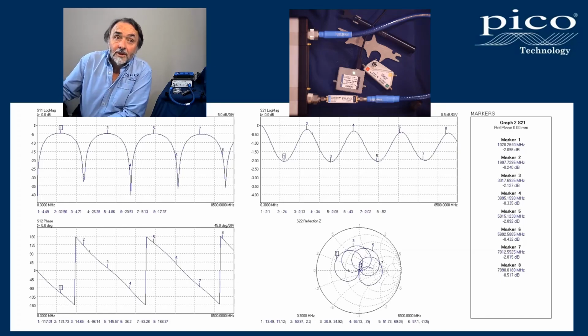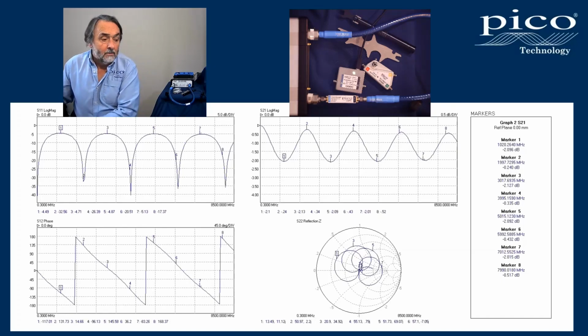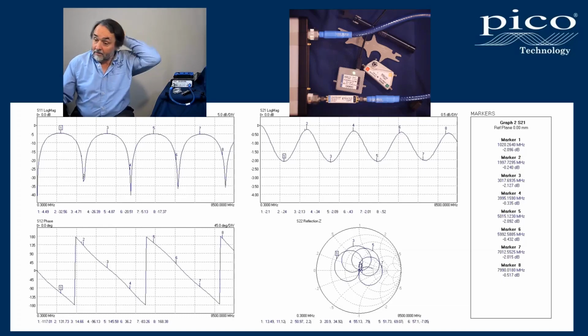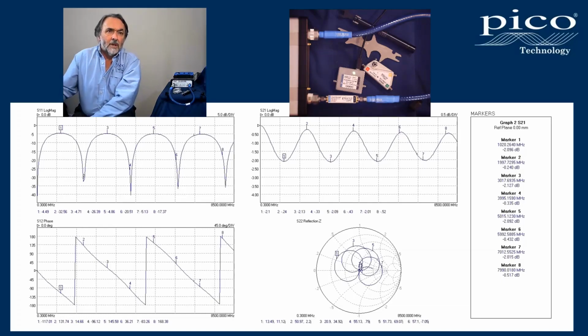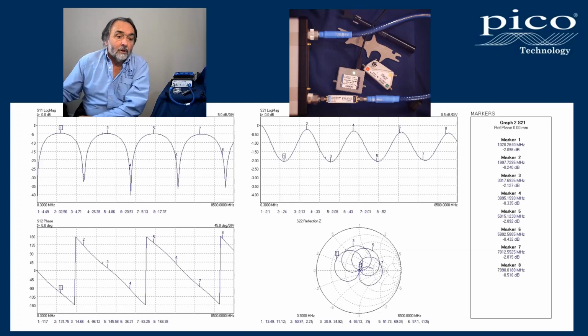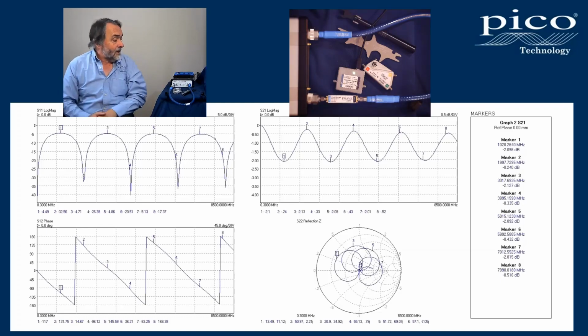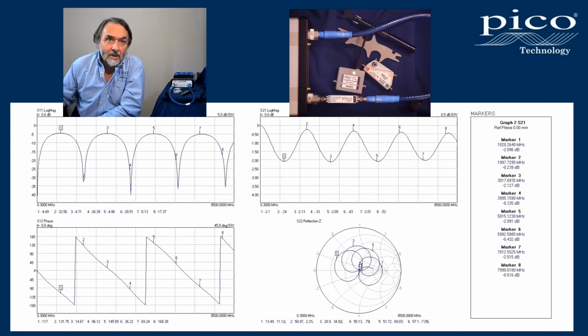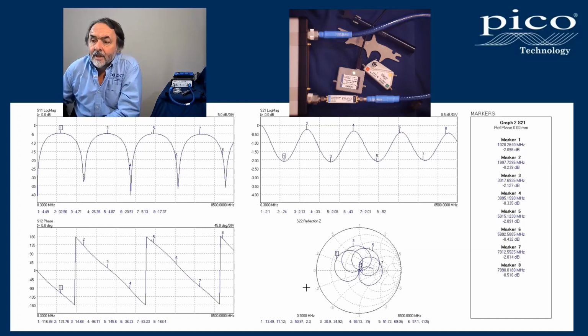We know what this check standard should measure, because the check standard comes with traceable measurement data from its own calibration, and so this measurement should match within the specification of the VNA. This measurement should match its own data. So let's load that data.